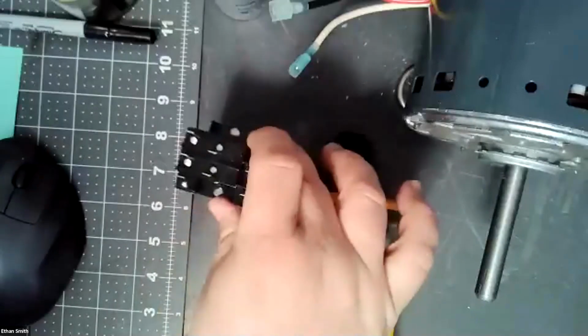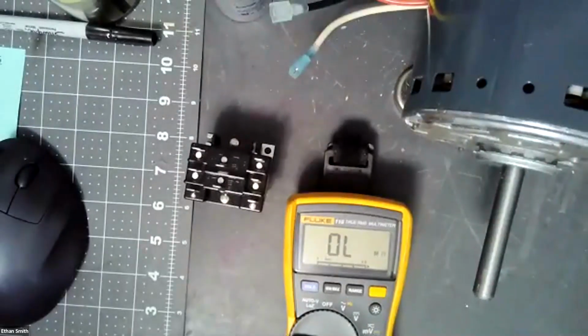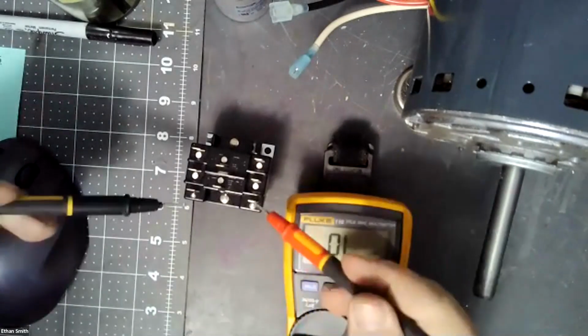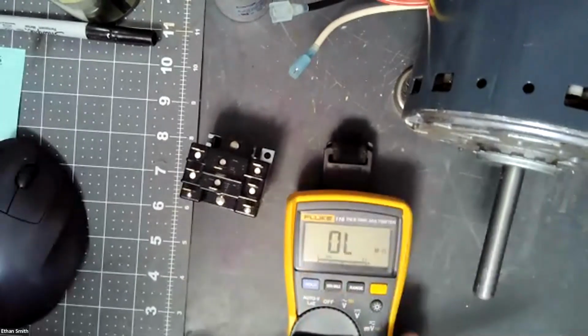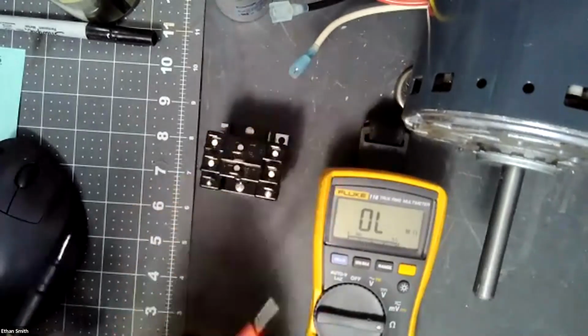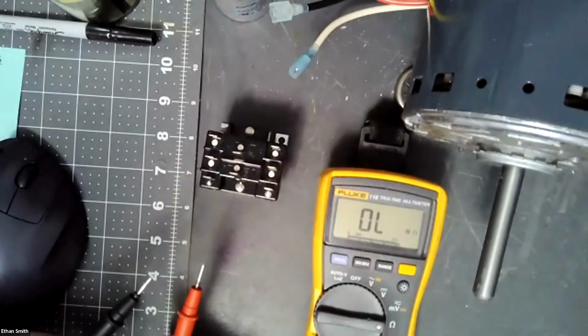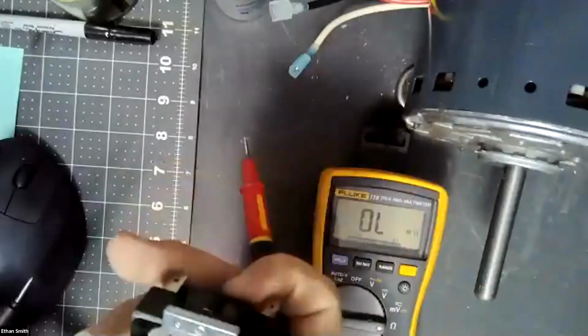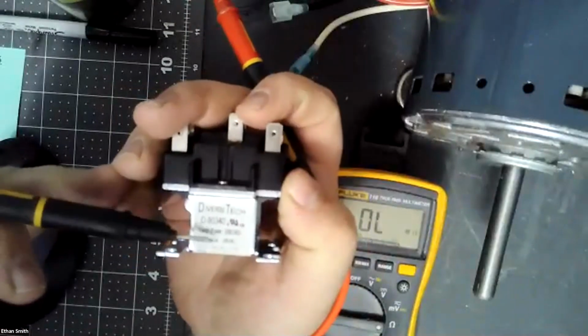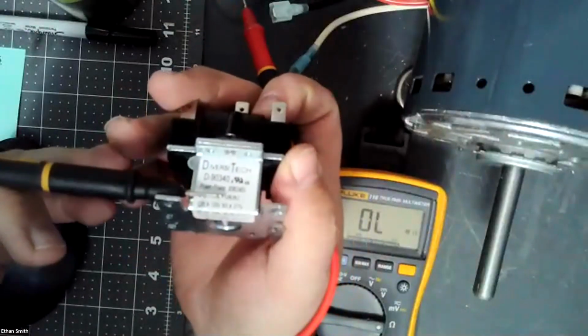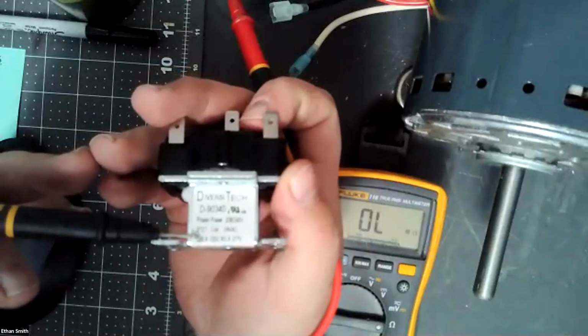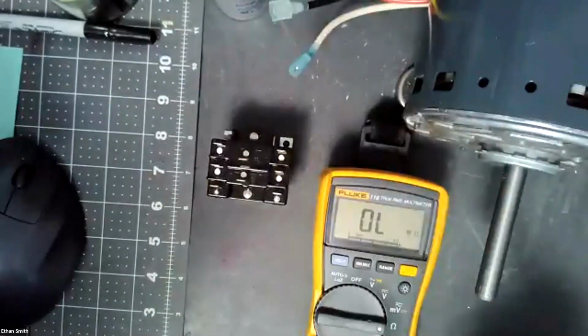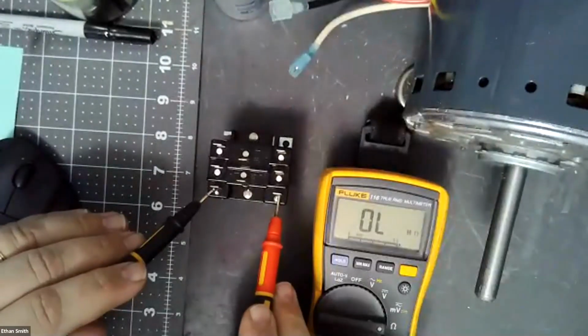So a couple different ways we can diagnose a solenoid. We know it's energized if it's getting power, so that one's pretty easy. We would just test a voltage across these two leads. But you can also test the solenoid coil by taking a resistance reading through it. Sometimes you know what that resistance reading is going to be. This one we do not. It just gives us our designation. It's a 24-volt coil, and it gives us our amperage ratings and our voltages here, but it doesn't give us a resistance reading. But we know it's a coil of wire. We should have some resistance through it. So this gives us a place where we can diagnose.